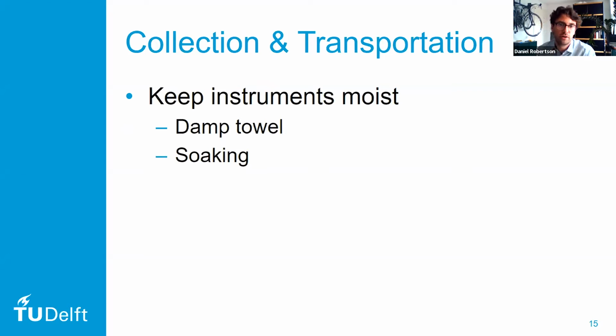Now, the first step is when the instruments are to be transported to the location where they'll be reprocessed. And the most important thing is to keep the instruments moist after using them. And this prevents the proteins and fats from drying onto the instruments, and that makes them much harder to clean. Now, it's best to use an enzymatic soaking solution. And this soaking solution has enzymes that will already start to break down some of the proteins and fats that are left on the instruments. Now, if this solution is not available, just plain water should be used.